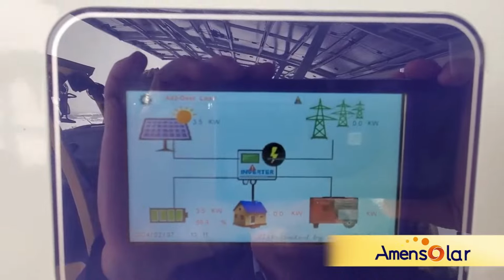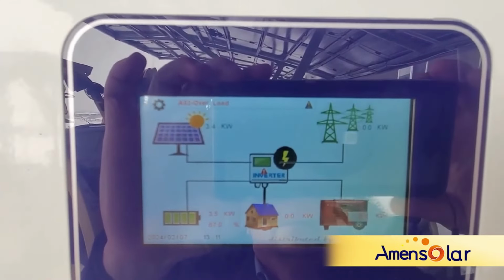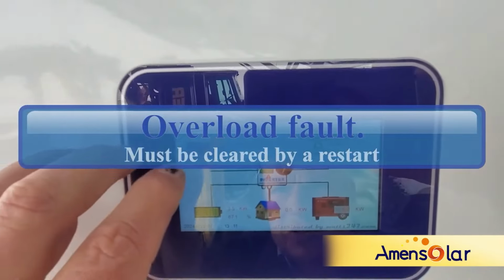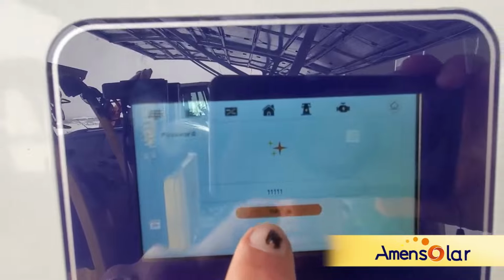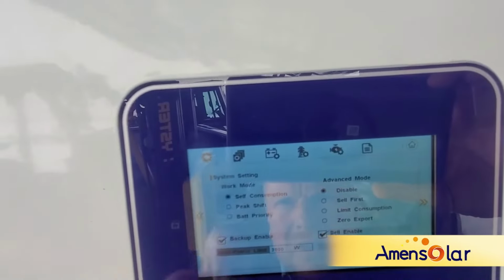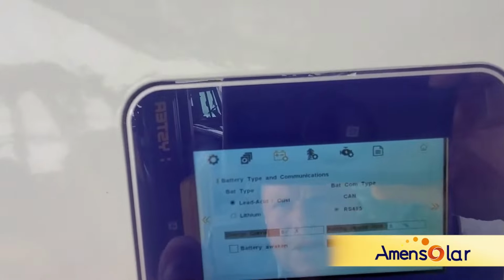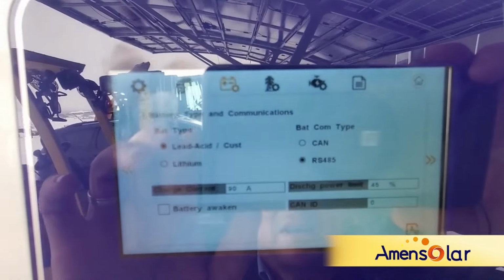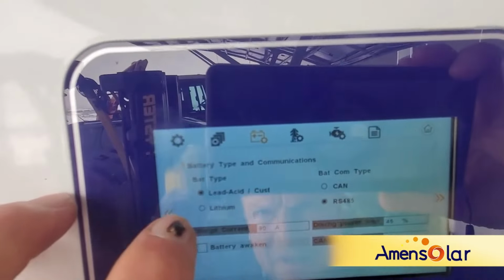And setting up for lithium batteries is pretty simple. Within a short while this should reset itself. So if we set it up for lithium batteries, we hit the little star button, put in 5, 1s, put OK, and click on battery mode. It's set right now to lead acid.